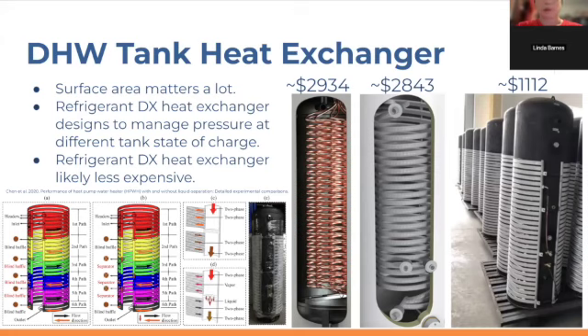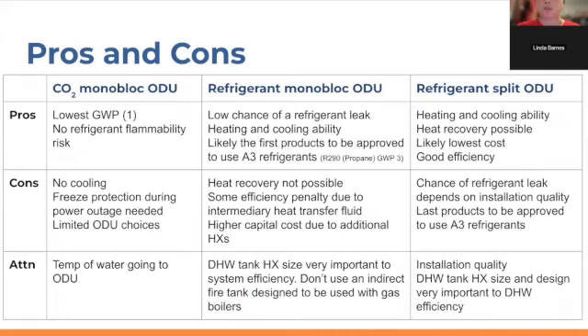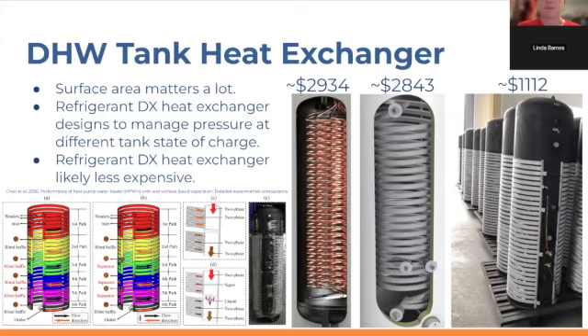So when I said that there's some price differentials between if you pick a refrigerant monoblock outdoor unit versus a refrigerant split outdoor unit style combi system, a lot of that cost difference, in addition to being in the outdoor unit, also happens to hit you on the domestic hot water side of the combi system. It's because the heat transfer fluid for a monoblock style system will typically be a water glycol mix, so that in the wintertime there's no chance of freezing. But you cannot have water glycol mix into potable water and have that be safe. And so it has to be an indirect fire heat exchange inside the tank where the water glycol mix circulates in a closed loop between the outdoor unit and the inside pipe of the slinky inside the water heater heat exchanger.